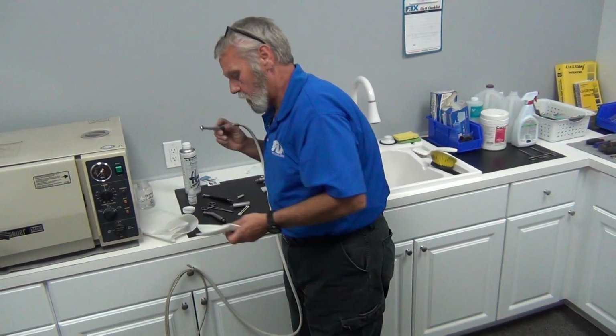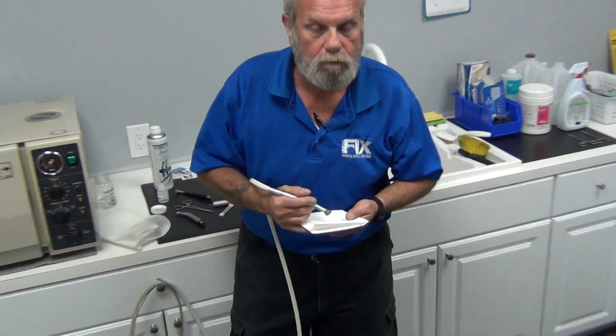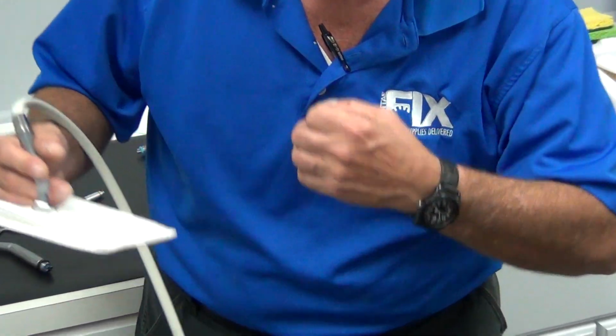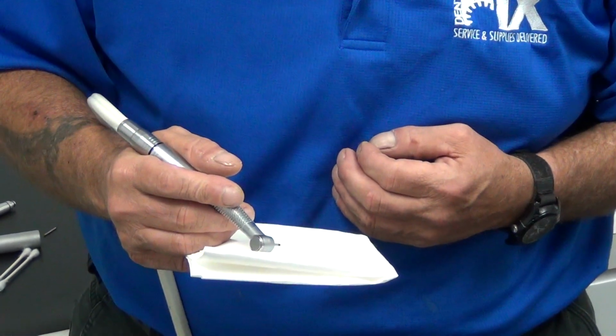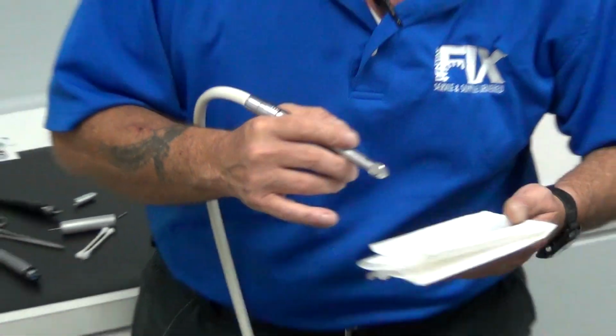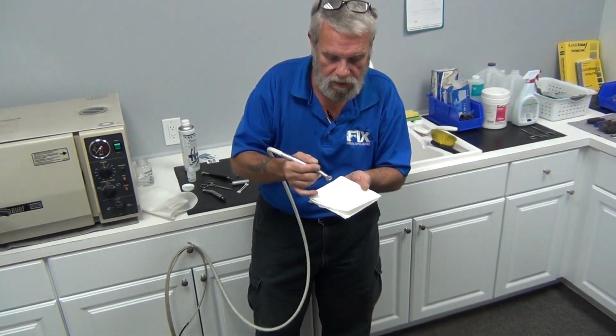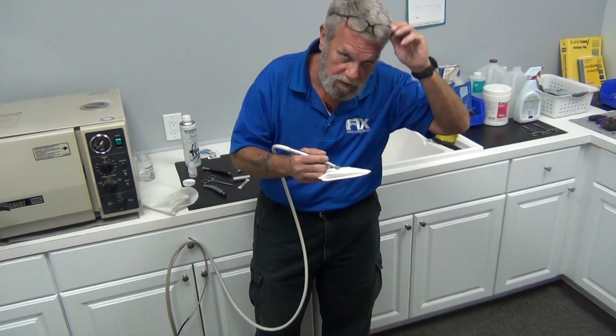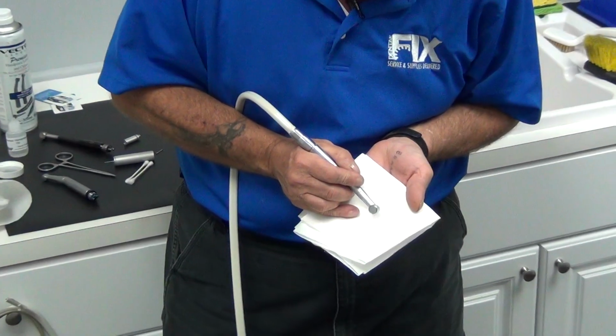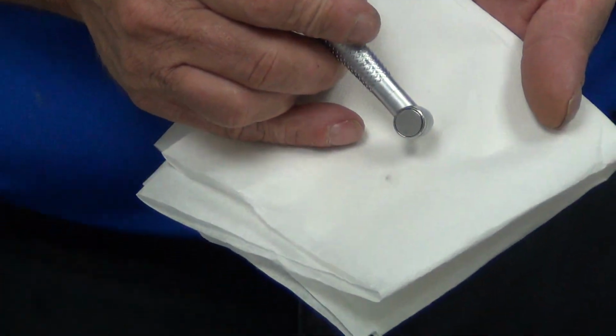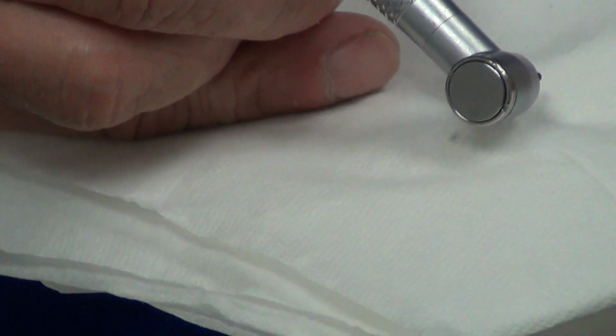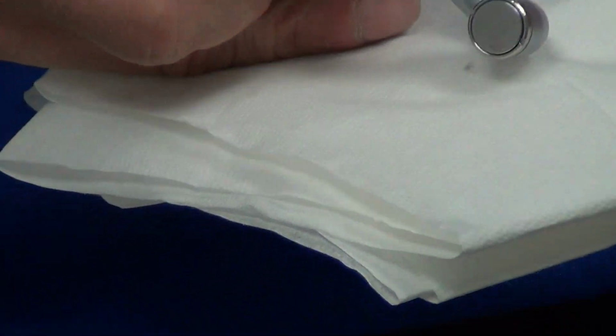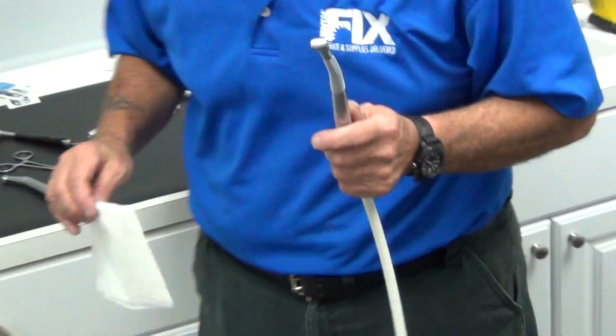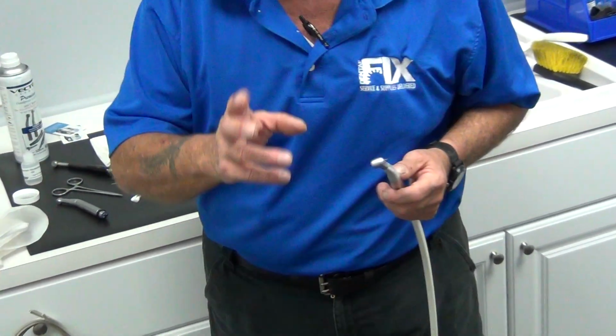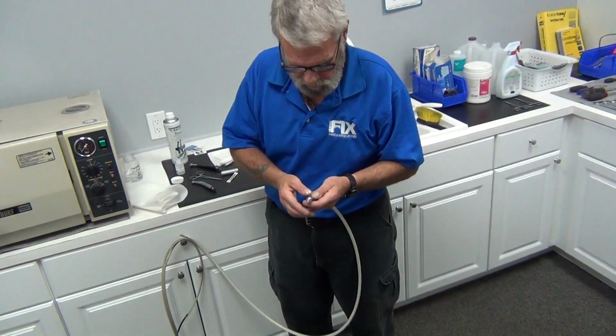Now, we're going to purge the unit. The oil that we put in, we're going to purge the excess oil out so that it doesn't gum in the sterilizer, and so that it broadcasts, meaning we get a good spray over all the bearings and all the impellers and all the working parts in the handpiece head. Now let's purge. Now we've purged and we've distributed the oil. Certain handpieces are going to purge with more debris coming out of them than others, okay?